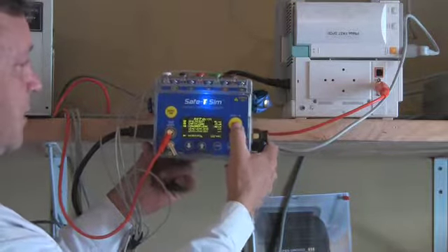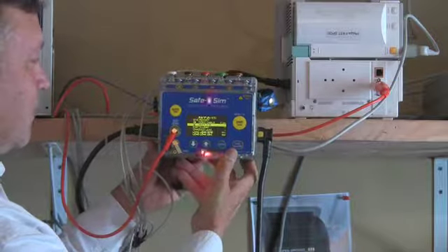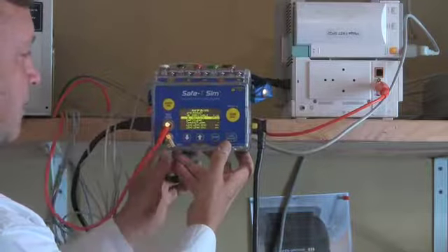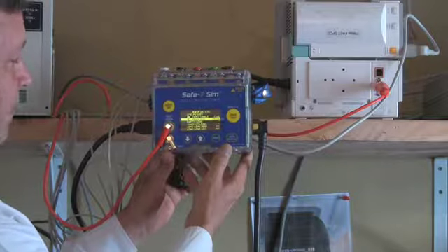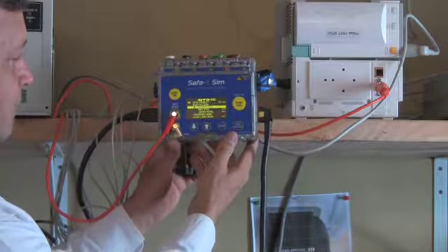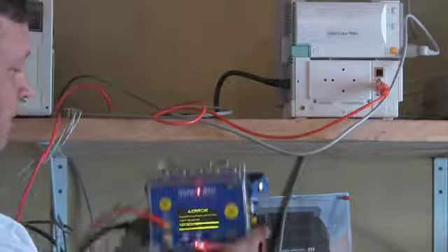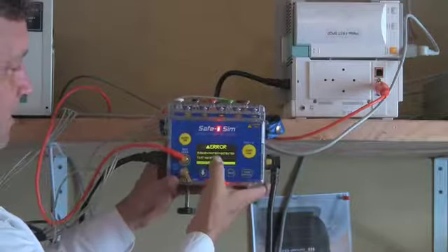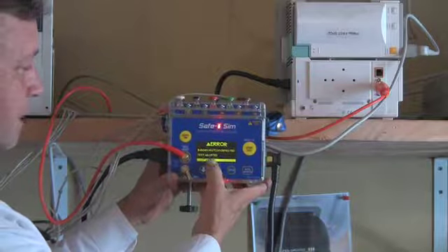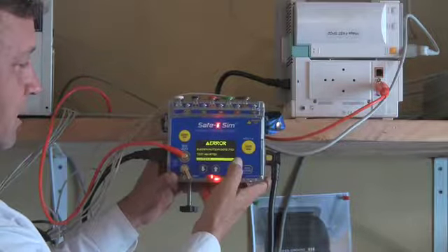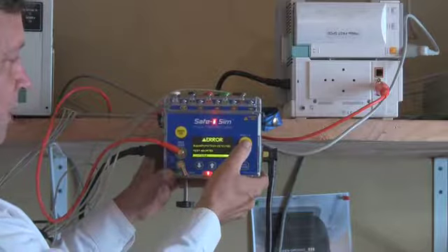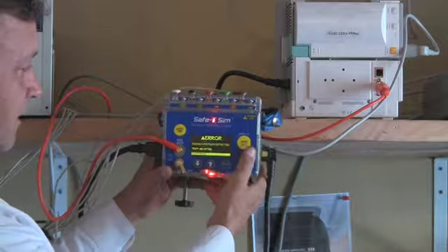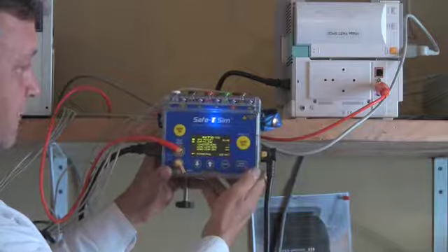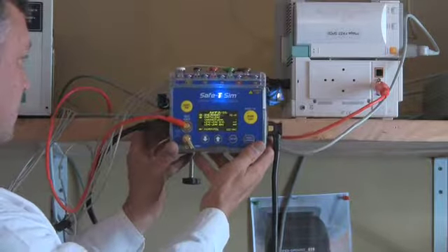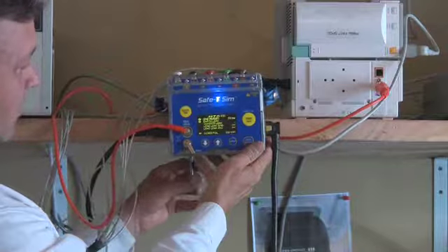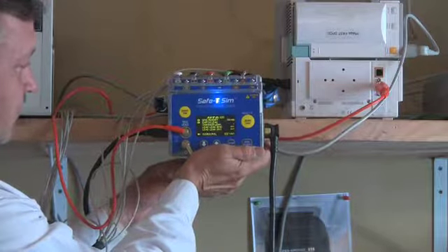So I'm going to do a quick demonstration of how that works. We're going to turn on the tester, we're going to run an actual test, and I'm going to drop the device a couple feet so you can see it. I dropped it a couple feet, it detected sudden motion, and it aborted the tests, meaning that it shut down all the relays to make sure that no damage would be done to the internal circuitry of the safety analyzer. As far as I know, that's the first safety analyzer ever built that has the ability to detect a drop before it hits the floor and protect its own circuitry.